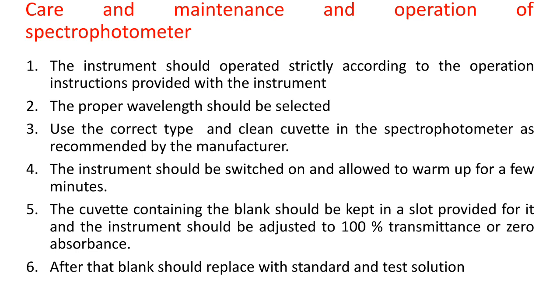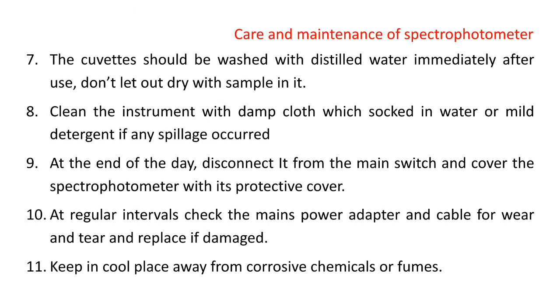The cuvette containing the blank should be kept in the slot provided for it, and the instrument should be adjusted to 100% transmittance or zero absorbance. That is called the instrument zero. After that, the blank should be replaced with a standard and the test solution. Next, the cuvette should be washed with distilled water immediately after use, and don't let it dry with a sample in it. So usually you should wash it immediately.